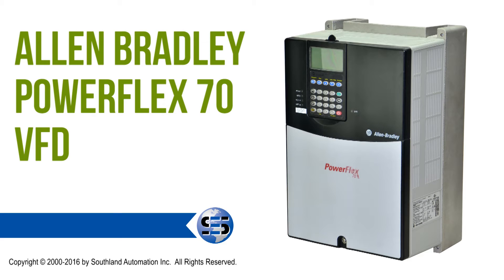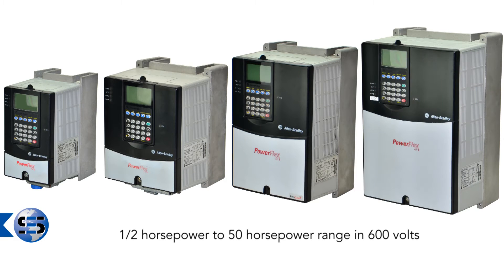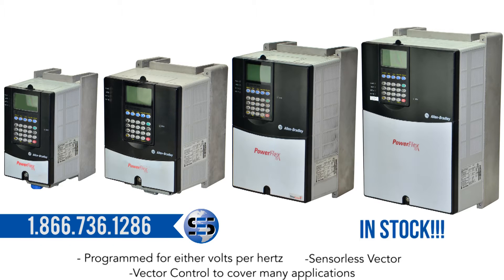The Allen Bradley PowerFlex 70 Variable Frequency Drive. The PowerFlex 70 comes in a half horsepower to 50 horsepower range at 600 volts. It can be programmed for either volts per hertz, sensorless vector, or vector control to cover many applications.